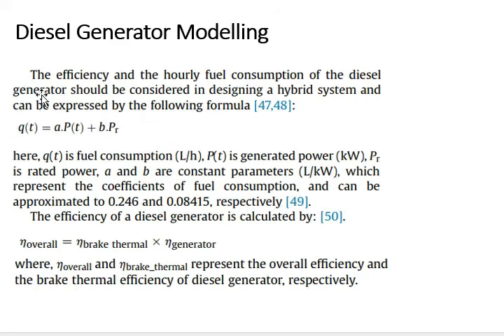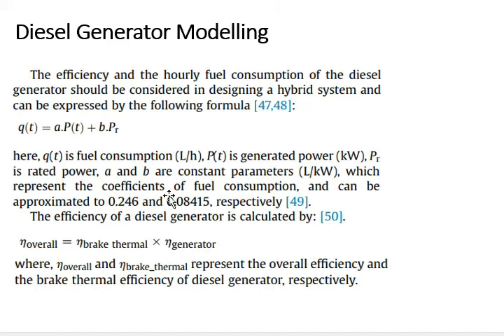Here, Q(t) is fuel consumption in L/h, P(t) is generated power in kW, P_R is rated power, and A and B are constant parameters representing the coefficients of fuel consumption, approximated to 0.246 and 0.08415 respectively. These values will be different for different generators.